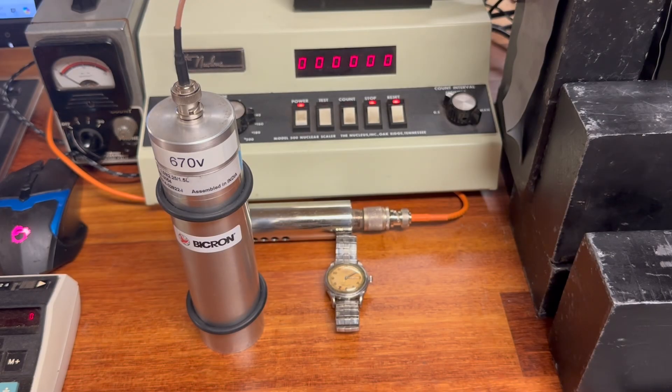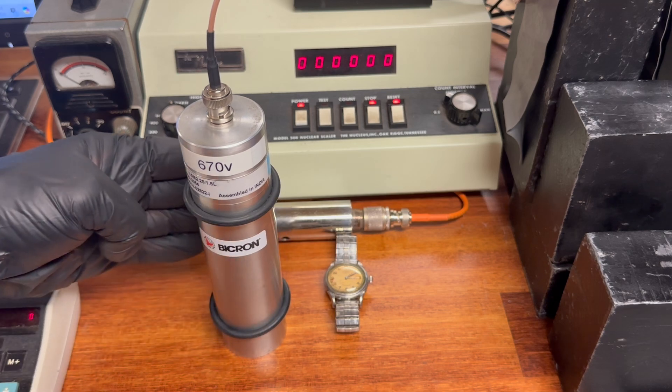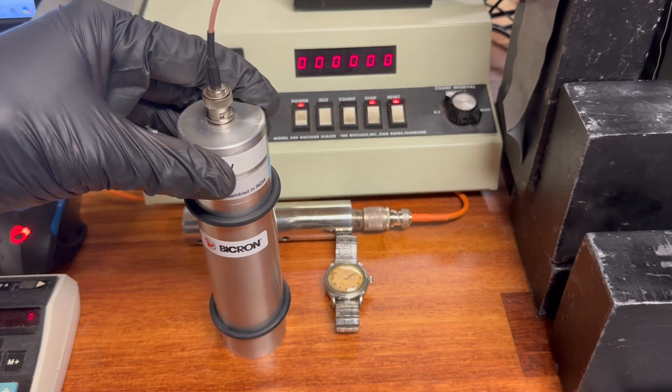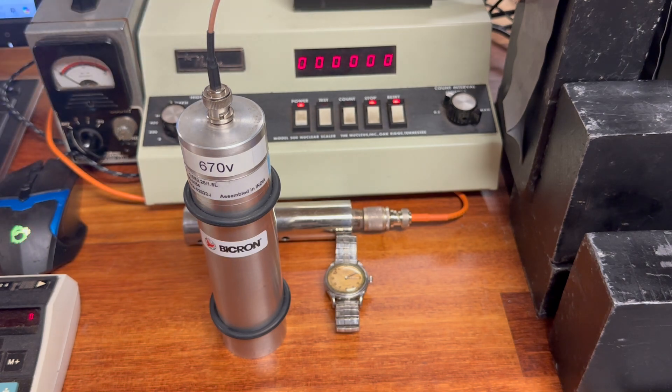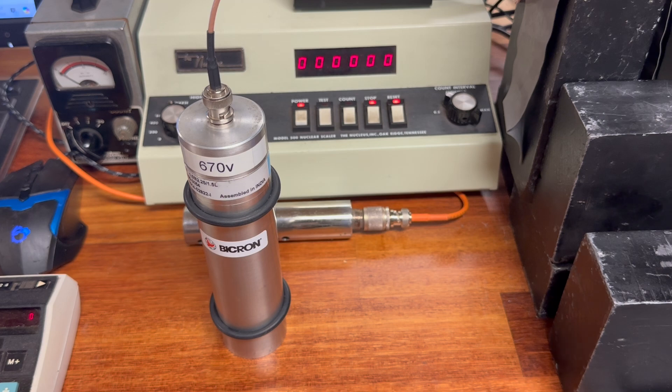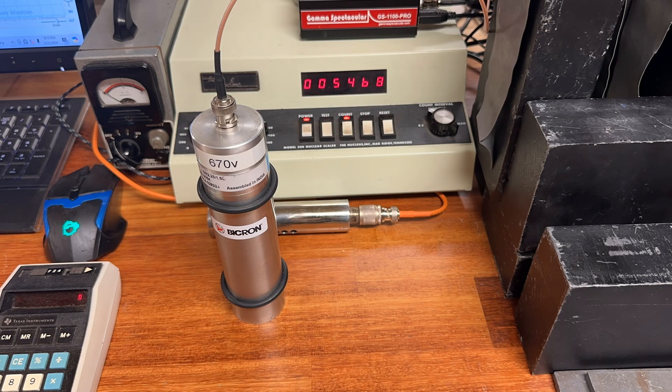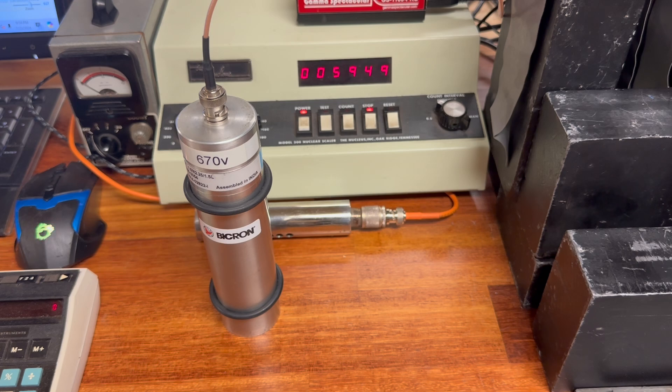So as a reminder, gamma scintillation detectors detect primarily only gamma radiation. Let's go ahead and do another test that we've done in other videos, utilizing the model 500 nuclear scaler made by the nucleus. This is going to give us a count rate timed at one minute, showing exactly how many counts we get per minute of gamma radiation coming from this watch. But before we do that, let's go ahead and set this watch across the room here. And let's go ahead and do a time count. It'll show us normal background radiation. We know that this particular shop averages around between 5,800 to 6,200 counts per minute background radiation. That's pretty close. 5,949 counts per minute.